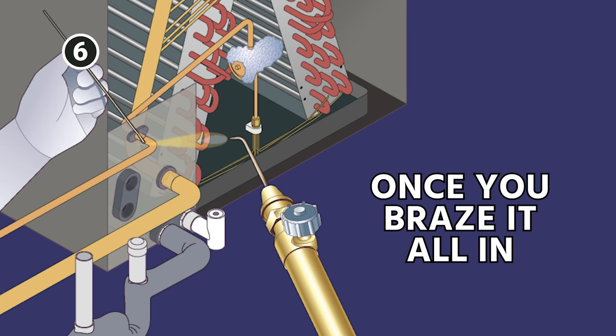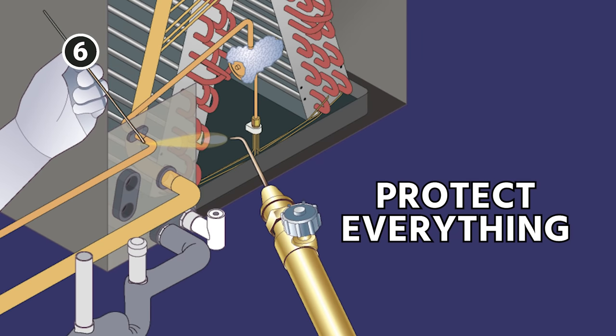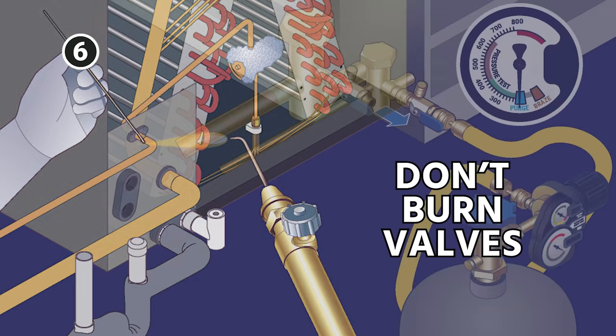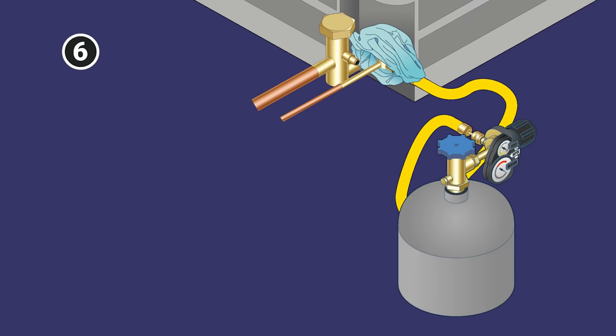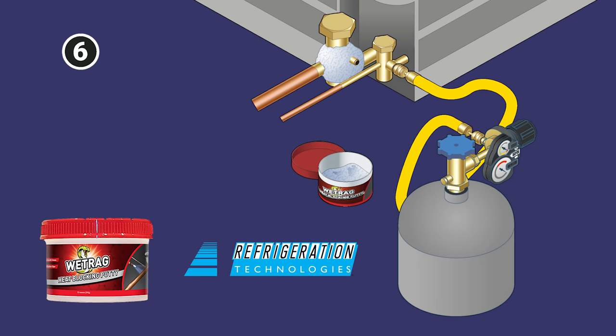Once you get everything all brazed in properly, again, make sure you protect everything. You're not burning paint, you're not burning valves, you're flowing nitrogen. That's very important. The brazing process is really critical on this. I like to use wet rag, even the product Wet Rag from Refrigeration Technologies to protect dryers.